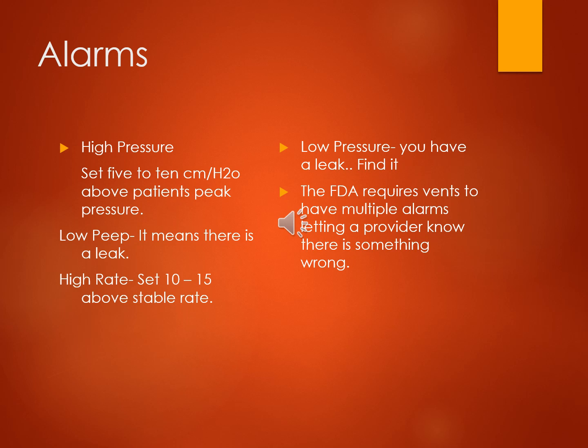Remember, the FDA requires vents to have multiple alarms. They are annoying sometimes, right? Because one time you'll just disconnect the patient to do a procedure, and then you go to plug them back in, and it's beepity beepity beepity beep. Well, it's going to keep beeping because it wants to have redundancy on there. It wants to make sure that you know that the patient is disconnected, and there's multiple different reasons why. So don't be mad at the ventilator companies, they're just doing what the government wants us to do.